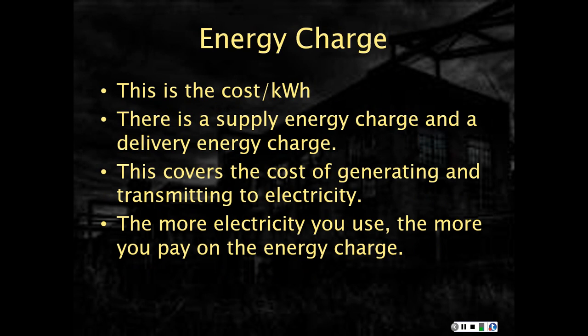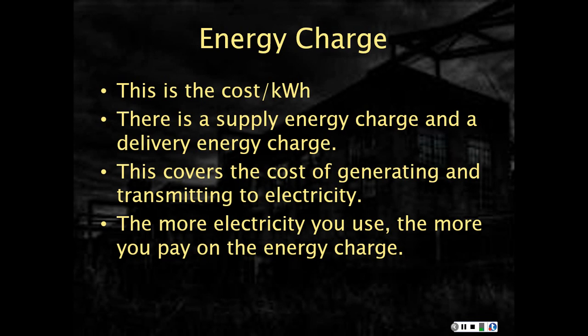The next major component within a consumption-based tariff is the energy charge. This is the cost per KWH and it covers both the supply side and the distribution side of the energy charges. On the supply side, this covers the cost of generation and transmission; on the distribution side, it covers the actual cost of getting the electricity to your building. This is based on a cost per KWH, so the more electricity you use, the more you pay.